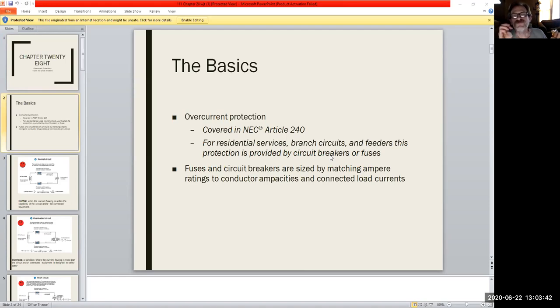Anyway, fuses and circuit breakers are sized by matching the amp ratings to your conductor ampacities and connected load currents. So say you were doing your lights and you did a given section of lighting on a branch circuit, and you have a 15 amp disconnect to it, a 15 amp circuit breaker, if you will, or a 15 amp fuse. Generally your wiring and everything else would be sized to handle 120 volts of up to 15 amps for that line. Anything over and above that 15 amps, and this device would disengage and kill the power feed to that line.